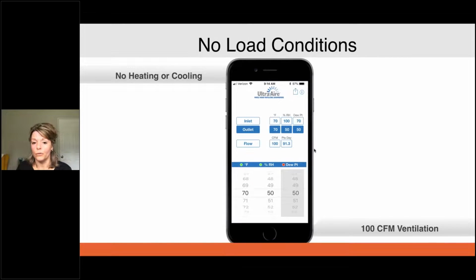And then we get into the no load conditions. So here we've got the 70 degrees and raining scenario. And again, at that 100 CFM, we need 91 pints of water removal a day at our no load conditions of 70 and raining. So that's just a tool you can play with. If you're more into grains than dew point, if you click on the little eye up in the corner, you can change it from dew point to grains. And you can also go from pints a day to pounds an hour.